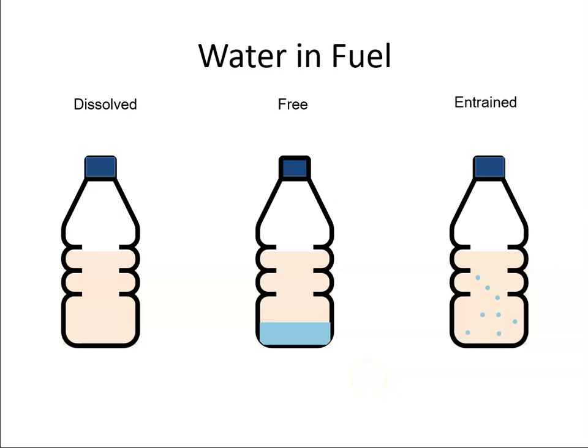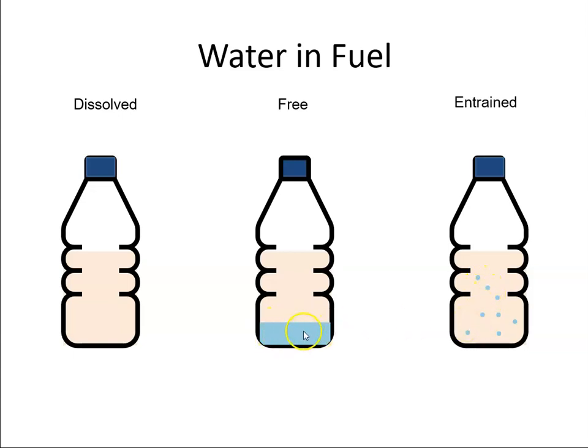Water can exist in fuel in essentially three states. First, dissolved — the water is fully dissolved in the fuel. Second, the water can have broken free from the fuel and becomes free water. A variation of that is where the free water exists in small tiny droplets, which we call entrained. At some stage these droplets might all come together to form a large gathering of free water.